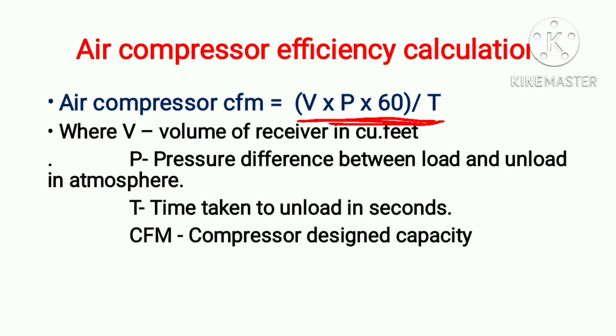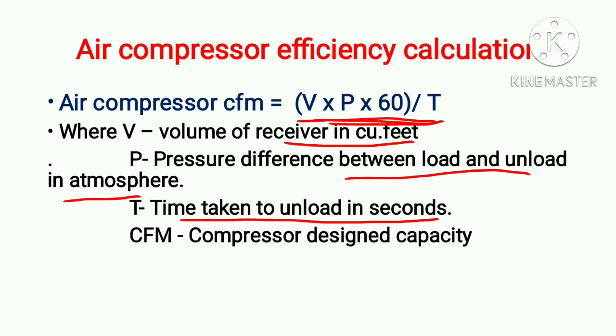The formula is: V × P × 60 divided by T. Here, V is the volume of the receiver in cubic feet. P is the pressure difference between load and unload pressure in atmospheres. T is the time taken in seconds between load and unload. CFM is the design capacity of the air compressor from the nameplate.